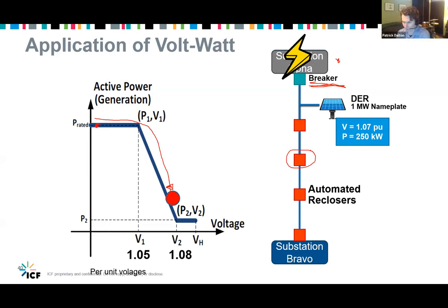And to this question about volt-watt control, it means reduced generation intentionally sometimes, which means that generation could be curtailed. That's absolutely right. Generation could be curtailed, and we want to be sure to use the function in a way that it's only for abnormal types of conditions. And this isn't a function that's activated on a daily, weekly, or even monthly type of basis. So it does result in curtailment, and it's a potential issue. There are studies out there that are looking at the potential losses here.